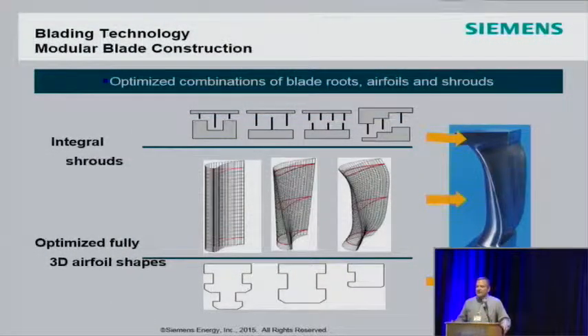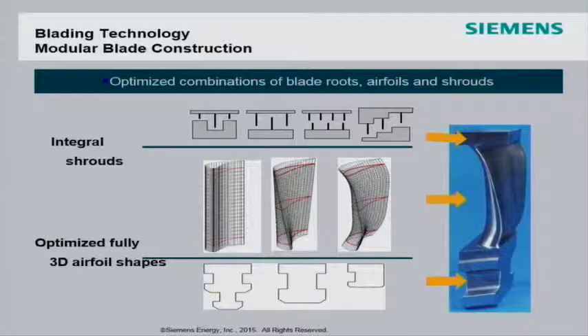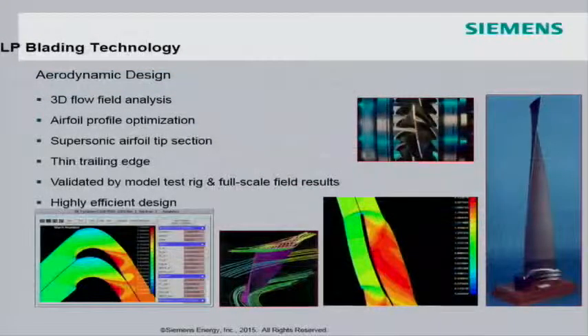So to give you a little bit idea here, this slide's showing closest to me here, the 3D blade here, the picture. You can see the radical shape there is our latest design. Again, being able to be manufactured due to advanced milling machines, literally 4-axis milling machines to do that, which you couldn't do, let's say, over 10 years ago. The interstage sealing showing up in the top there. So literally there you would do a different type of configuration or add maybe more seals to direct more steam through your steam path and get more work out of your blade path.